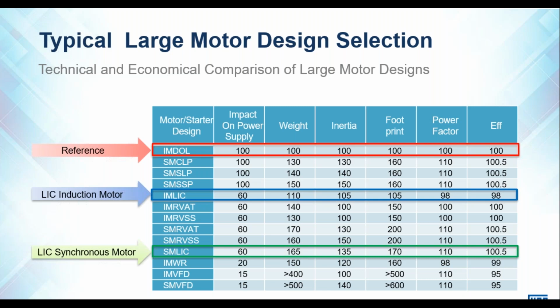Okay, just to close this section off, we have a technical and economic comparison of the large motor designs. I've just focused on 3 of them to save time, but we've used the induction motor direct online as our reference, and we've compared against the parameters of impact on power supply, weight, inertia, footprint, power factor, and efficiency. You can see that if we make that reference as 100, if you compare it to a low inrush current induction motor, the impact on the power supply is obviously reduced. So we put that at 60%.